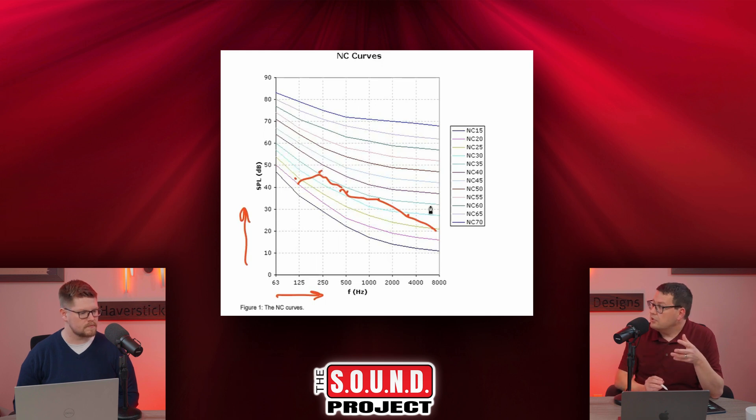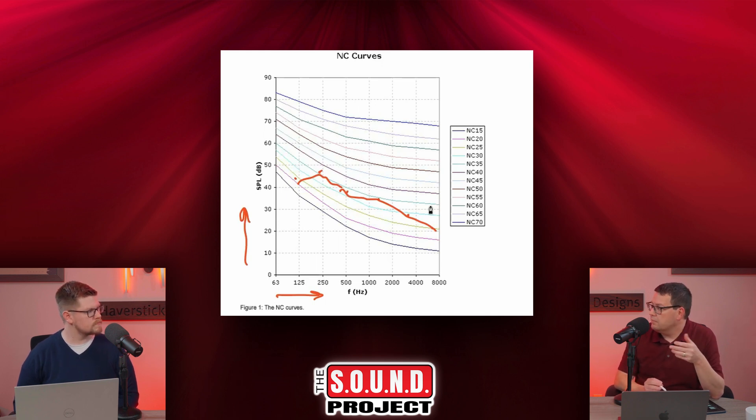HVAC contractors can actually design to an NC requirement. For a studio, the maximum NC we would want is 20. If we can get it lower, that's even better, but NC 20 is the maximum we would recommend. Anything louder than that is going to be picked up very easily when you're trying to record, and it could also be a distraction when you're mixing.